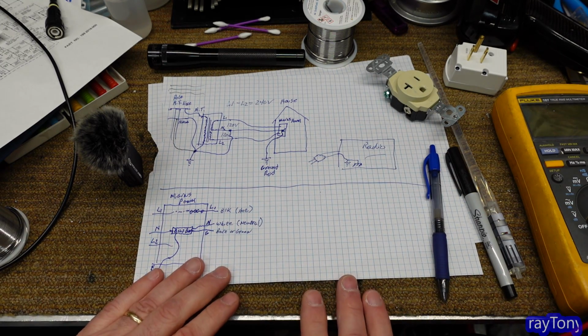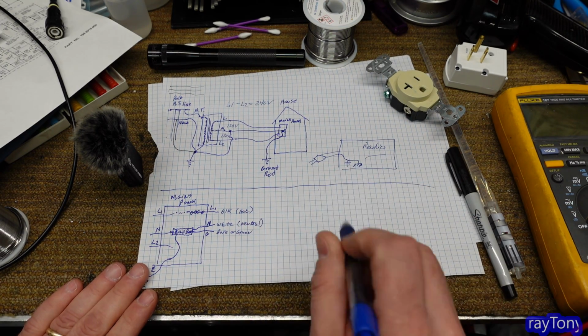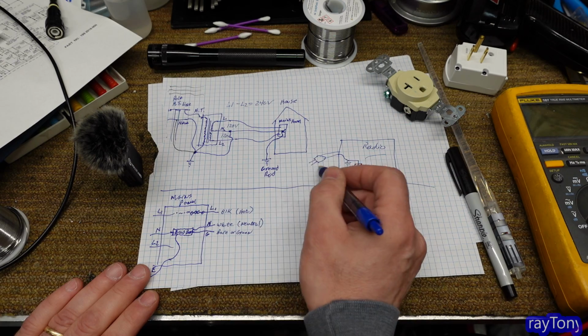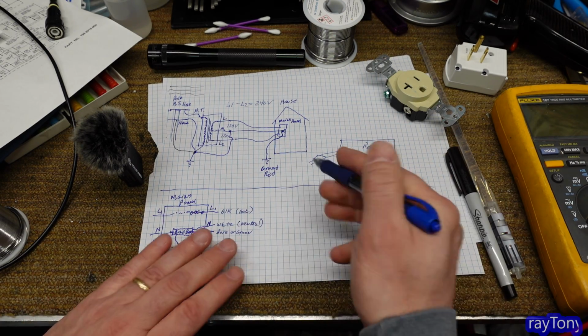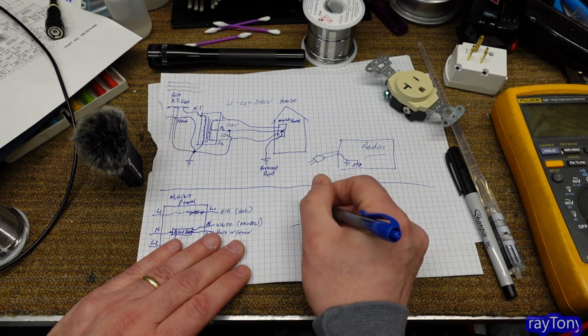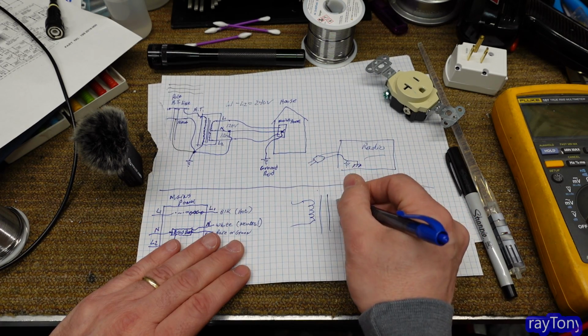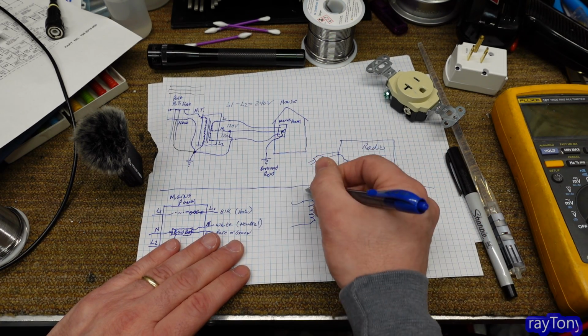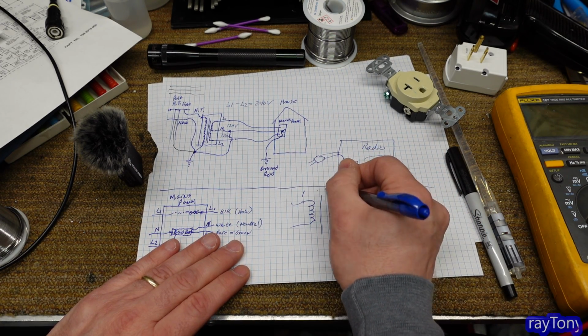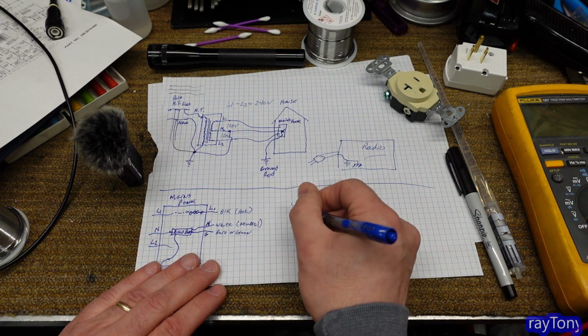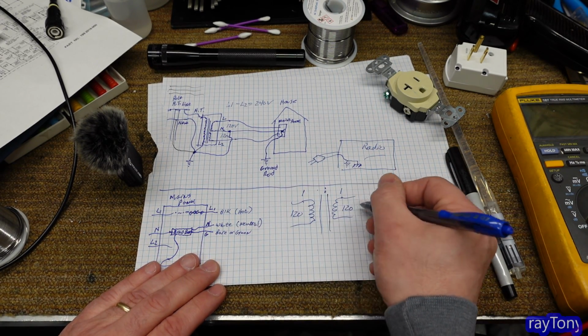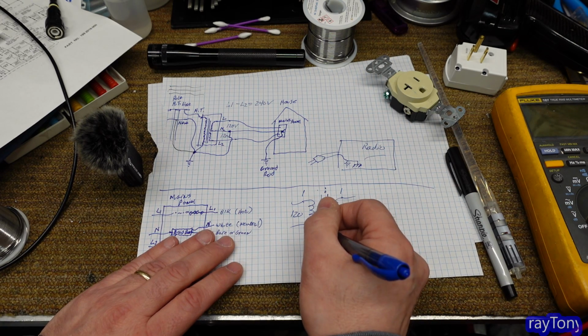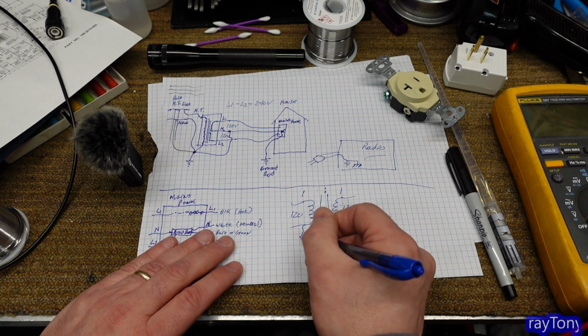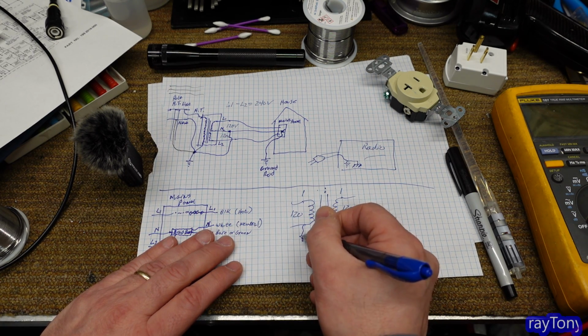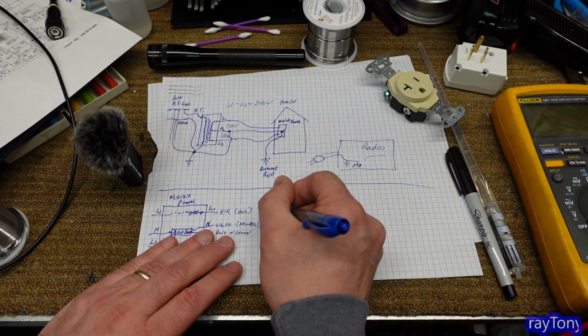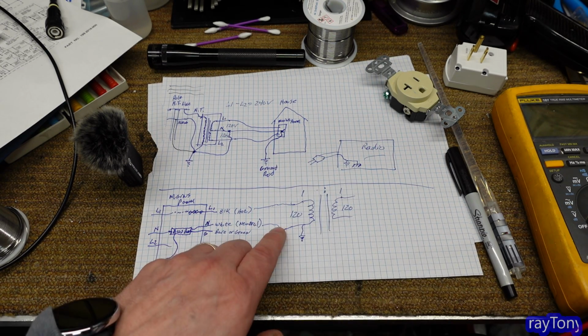So what people will do is they will put an isolation transformer between this plug and the mains. An isolation transformer is just what it says - you have a primary and a secondary, and it's a 1-to-1 winding. So if I put 120 in, I get 120 out. This side, your neutral's bonded to your ground and everything here, and your hot goes into here, just like that.